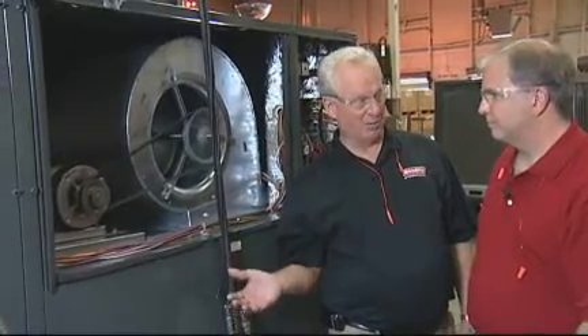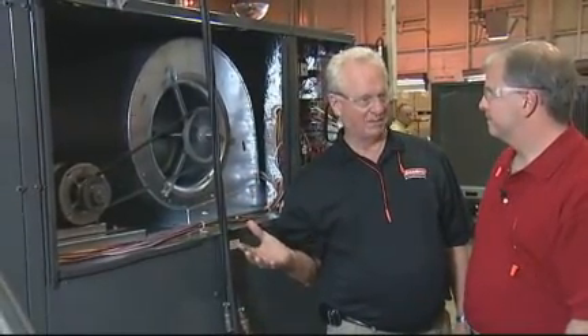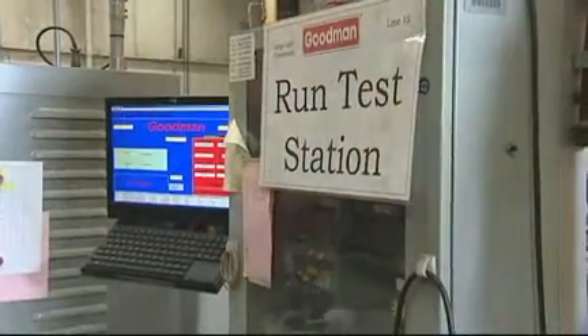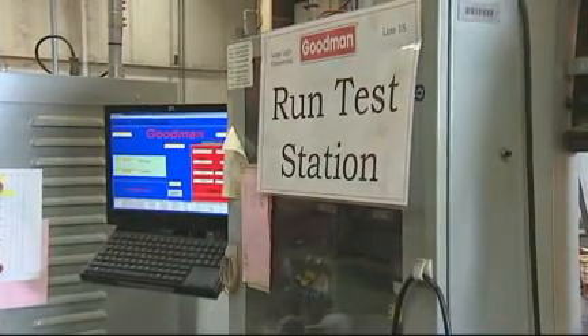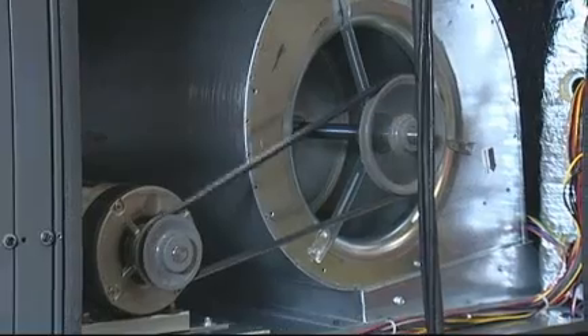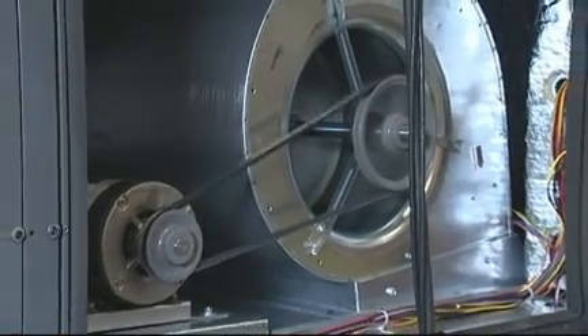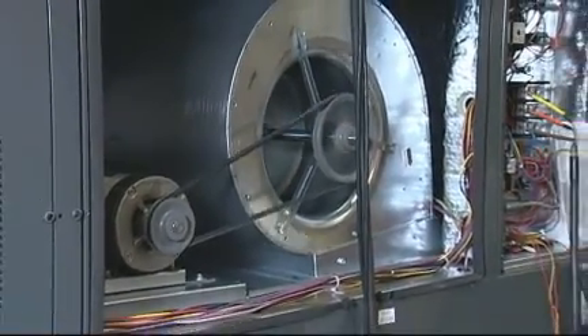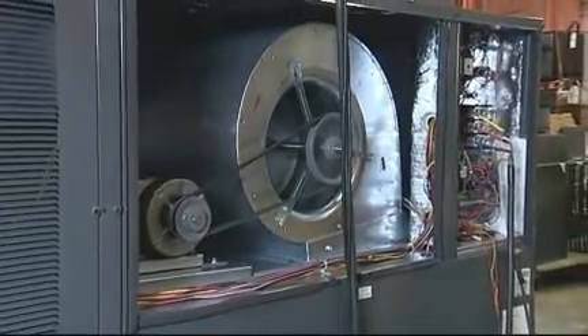This is the run test. Now these units are bigger units, 7.5 to 12.5 tons. This run test has a duration of 7 minutes. We programmed every possibility of error failure into the run test to make absolutely sure that once this gets a passed run test record, there's nothing possibly wrong with it. Okay, are you ready for the granddaddy of them all? The big one? The 20-ton unit. Let's go see it.